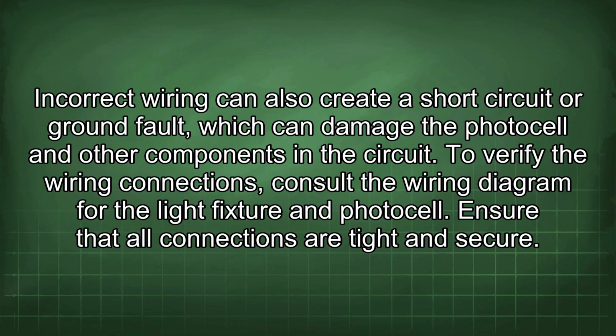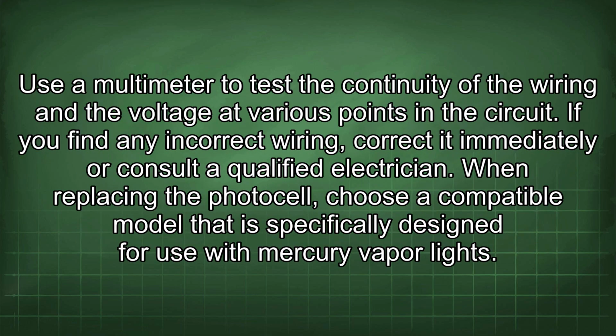To verify the wiring connections, consult the wiring diagram for the light fixture and photocell. Ensure that all connections are tight and secure. Use a multimeter to test the continuity of the wiring and the voltage at various points in the circuit. If you find any incorrect wiring, correct it immediately or consult a qualified electrician.